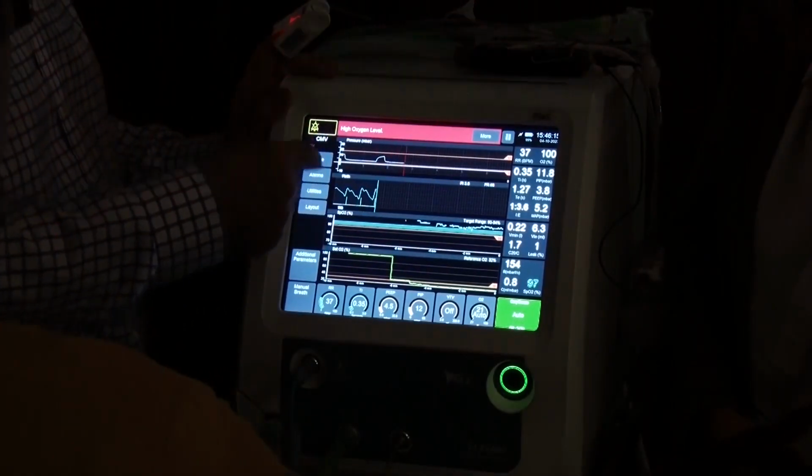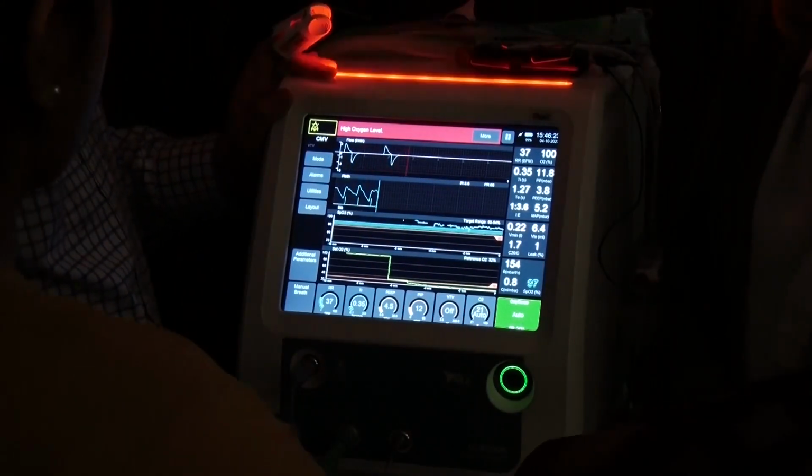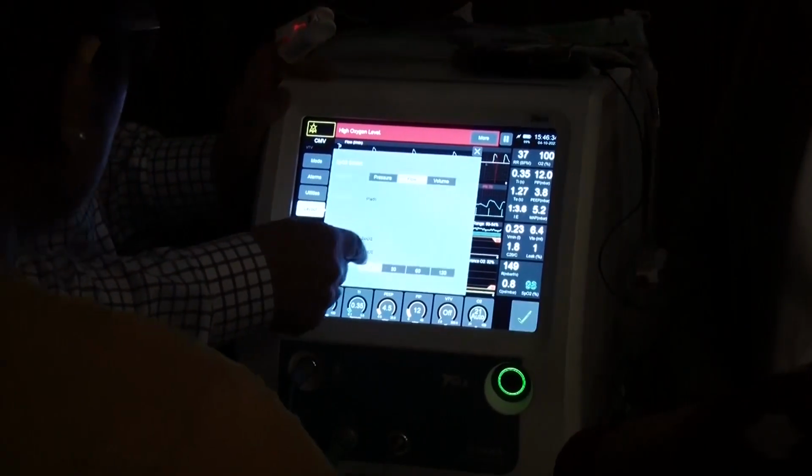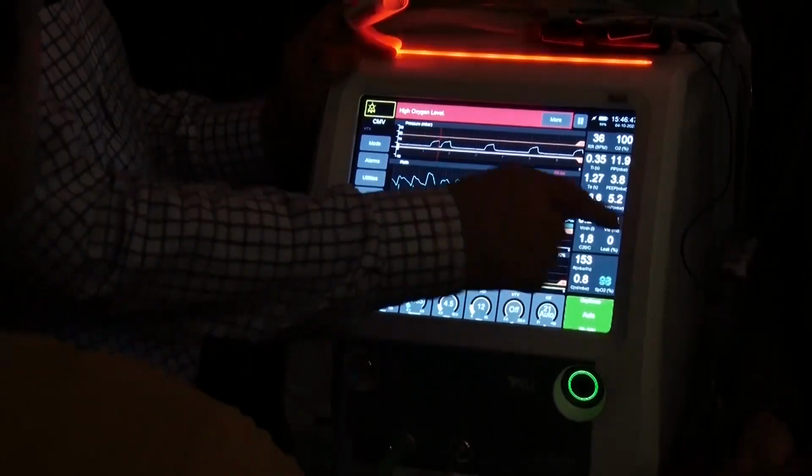So when it's on, it defaults to this one, which only gives you one of the ventilator waves. If you want to see that, you can't get it all in one screen. So it depends on how stable your baby is. If your baby's very stable, you can have pressure or volume here quite easily, and then see all the oxygen ones. But if you're needing to see all the volume data, then you probably need to have just the saturation graph out. But you won't see your oxygen.